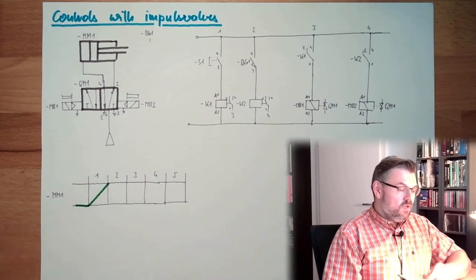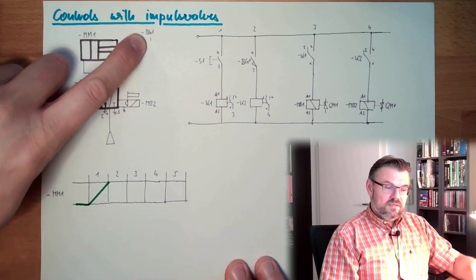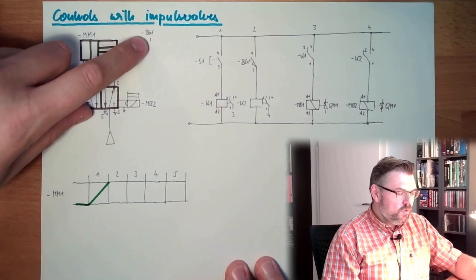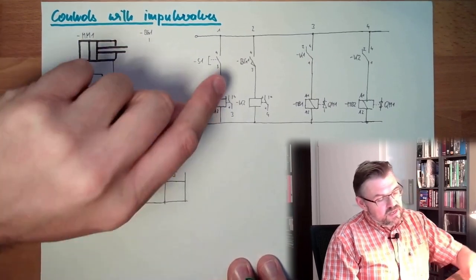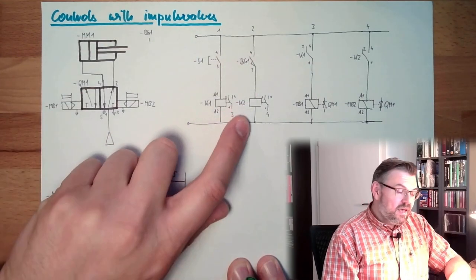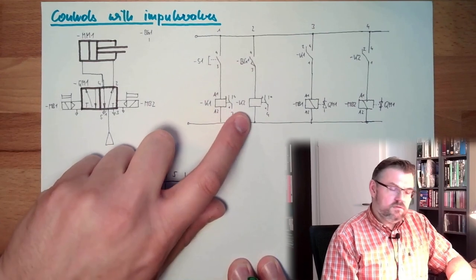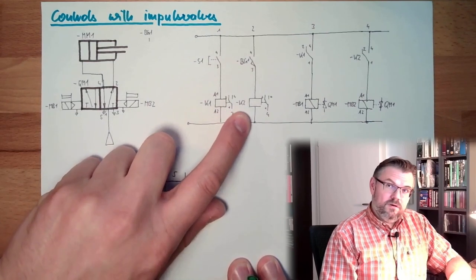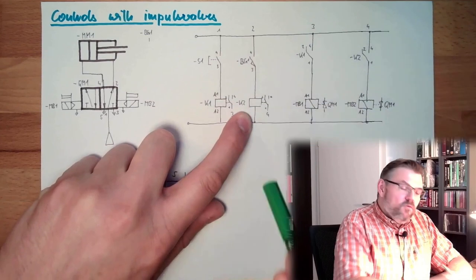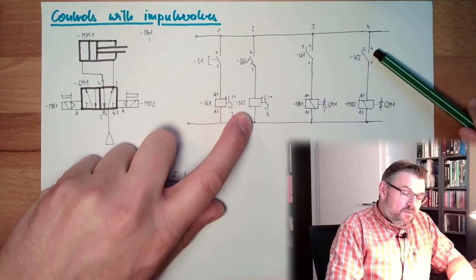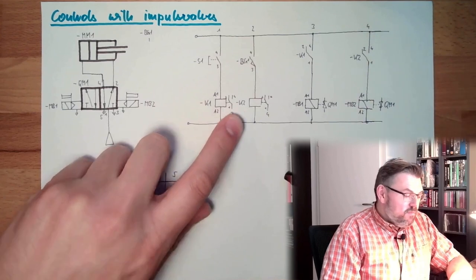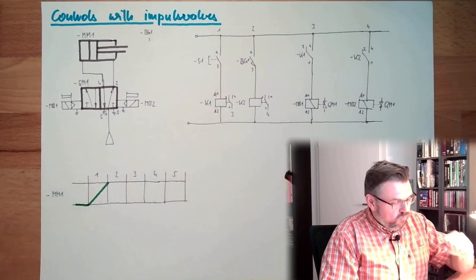What is happening now? Now BG1 is pressed, okay? Now BG1 is pressed. And if BG1 is pressed, it will close here. This K2 will be energized. We are closing here to the normally open contact. It's closed. Energize MB2. MB2 is energized.